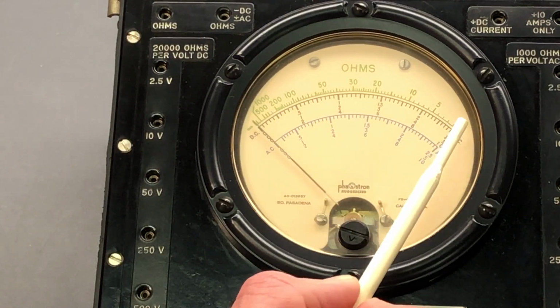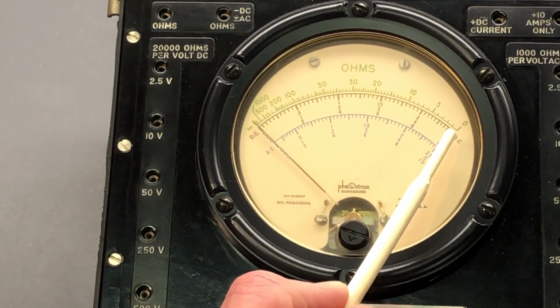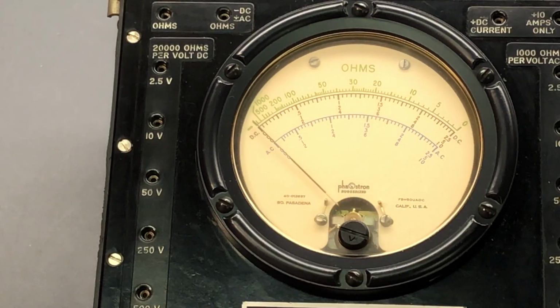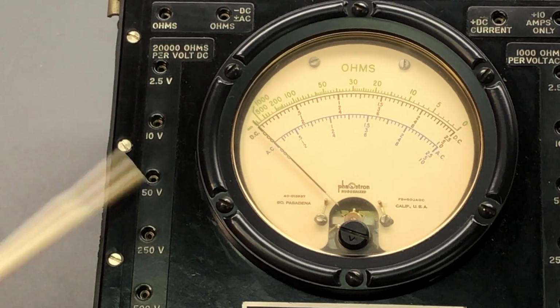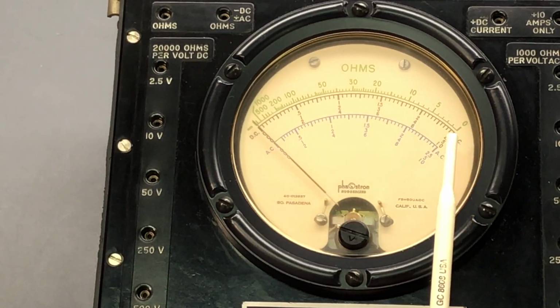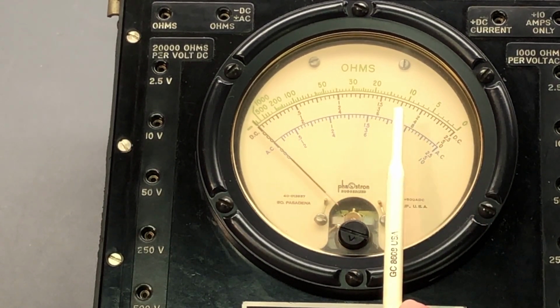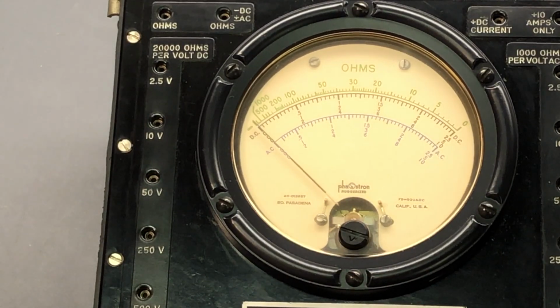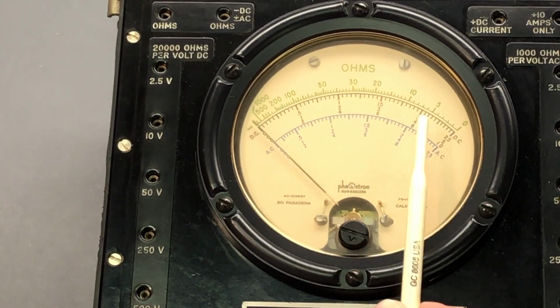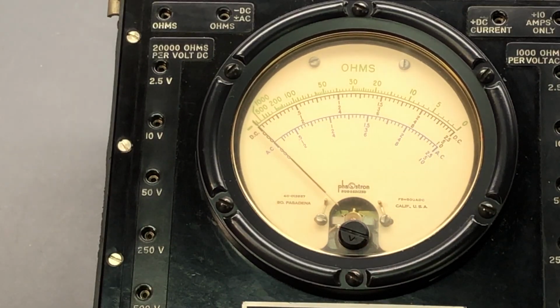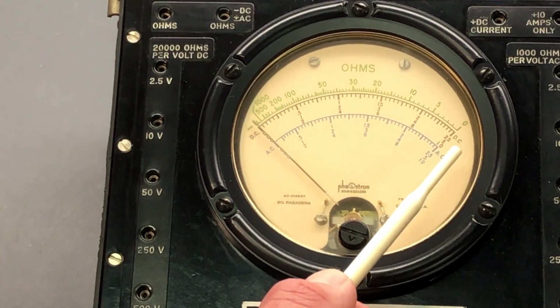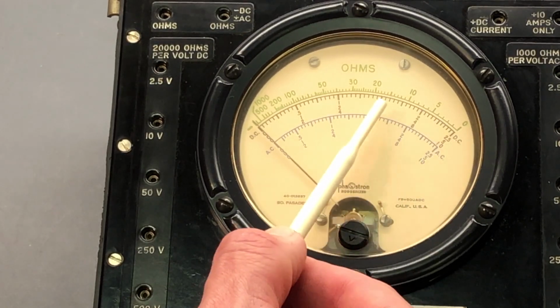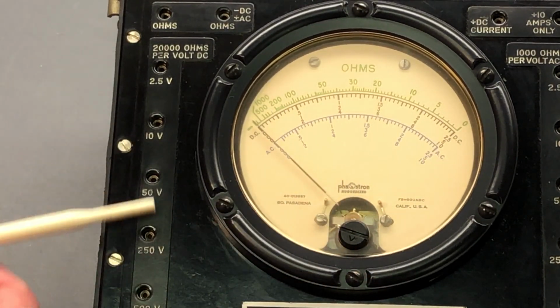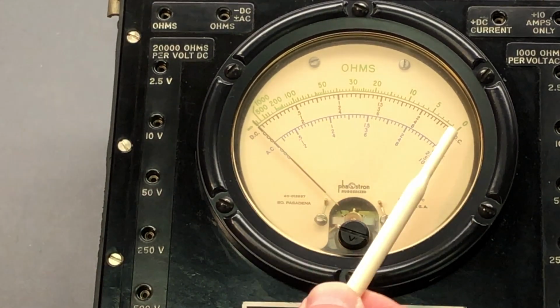So you do need to change which scale. You're not reading the 2.5 to 1.5. So just a slight difference on which scale you read on for the 5,000 volts. But for any of the other ranges, for example, if you're on 50 volts over here, then you read on the 5 becomes 50, 4 becomes 40, 3 would be 30, and so on. If you're on 500 volts, then the 5 is 500 volts, 400 volts, 300 volts, and so on. 2.5 volts here is very easy because you have 2.5 to 1.5, and you're reading that directly. So some of these higher ranges, you're just basically adding some zeros to the numbers that are on that scale.